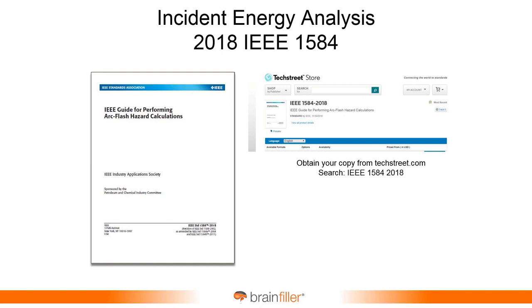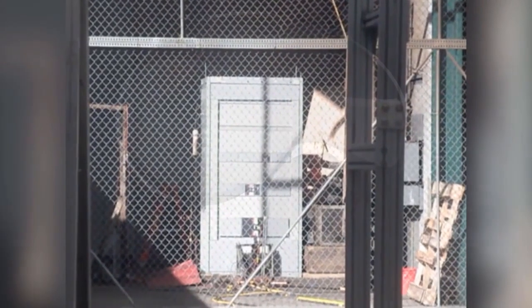So this is part of the incident energy analysis. And it wouldn't be complete if I didn't have at least one video showing an arc flash. And so this video that you're about to see is an arc flash that I staged. It was part of a pretty big project years ago. It was 50,000 amps of short circuit current, 480 volts. It was a really large switchboard. So let's see what this looks like.